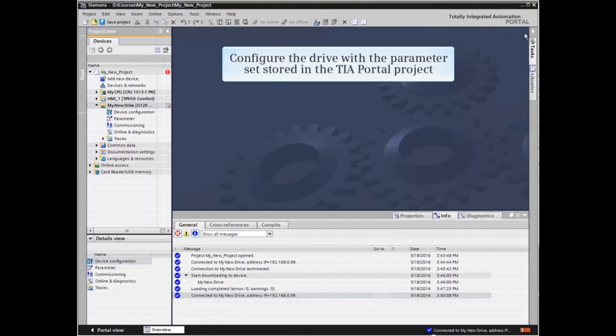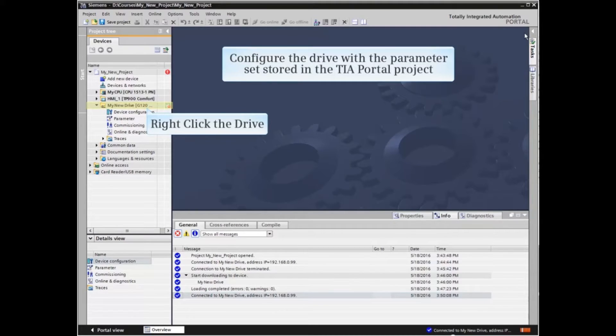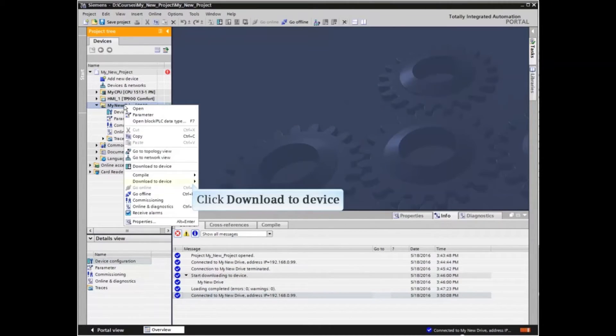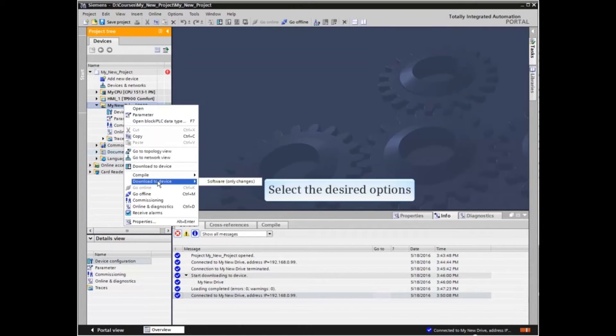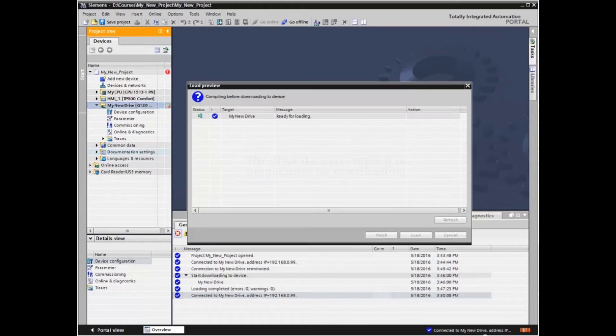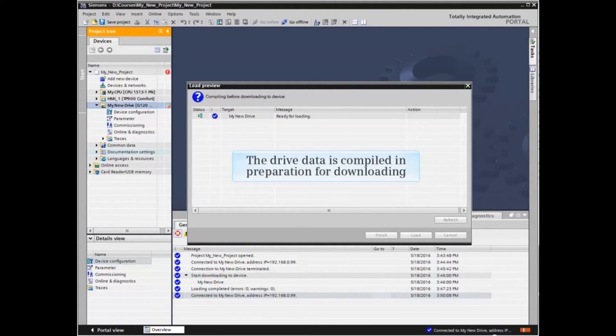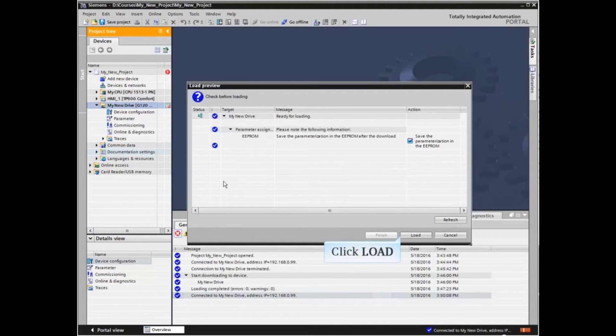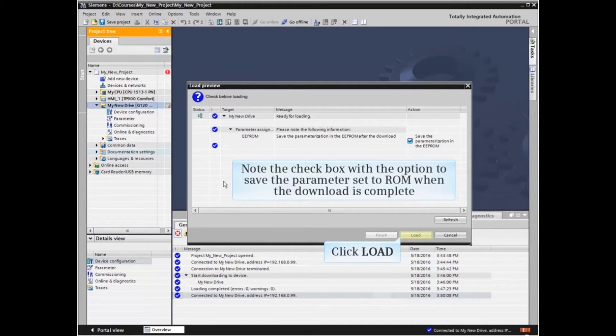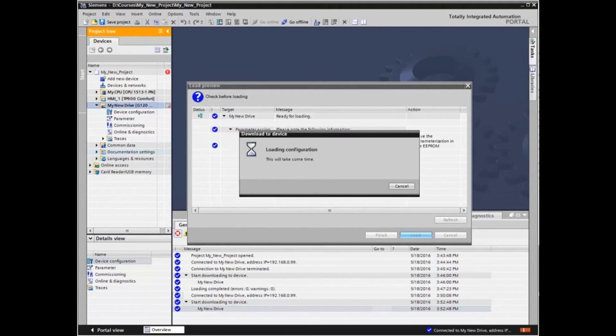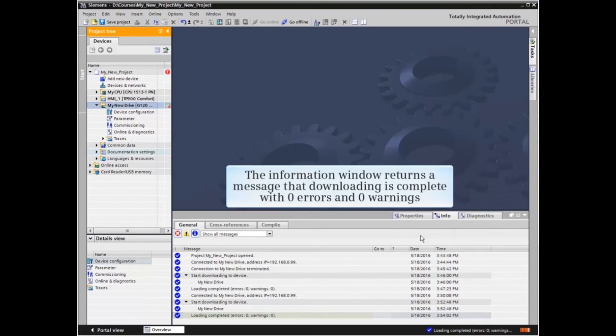We now want to configure the drive with the parameter set stored in the TIA Portal project. Right-click the drive element in the project tree, click Download to Device, and select the desired options. The drive data is compiled in preparation for downloading. When compiling is complete, click the Load button. Note the check box with the option to save the parameter set to ROM when the download is complete. The information window returns a message that downloading is complete with zero errors and zero warnings.